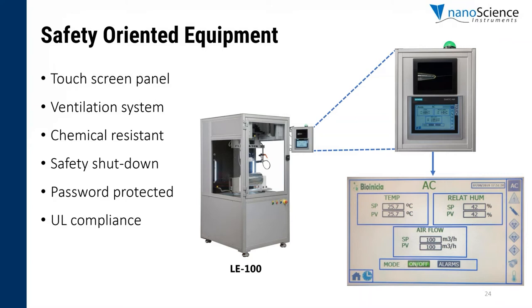Another feature I'd like to mention is that all units operate outside of the fume hood, thanks to the ventilation system implemented in all of the units. This allows the solvent to be properly removed from the chamber during the spinning or spraying process. The chamber is also made of stainless steel, aluminum, and glass frames and enclosure.